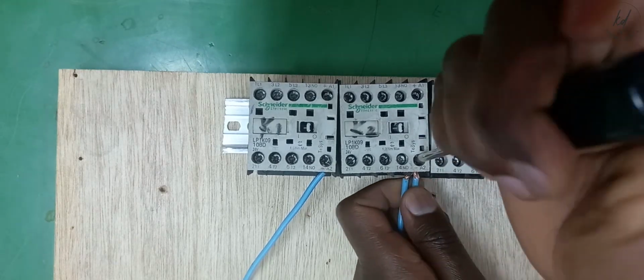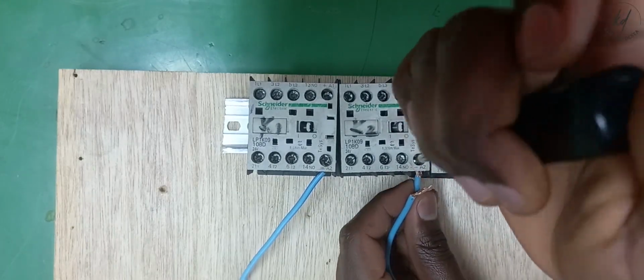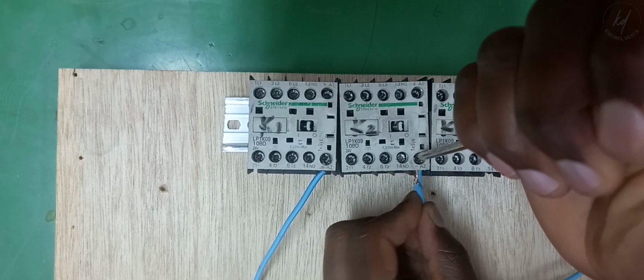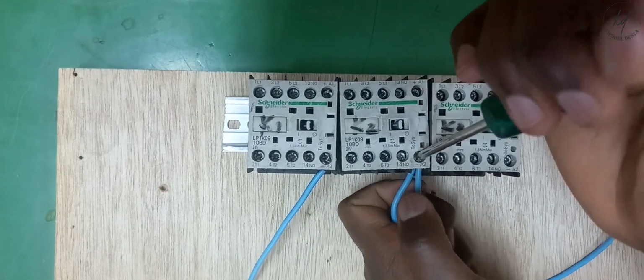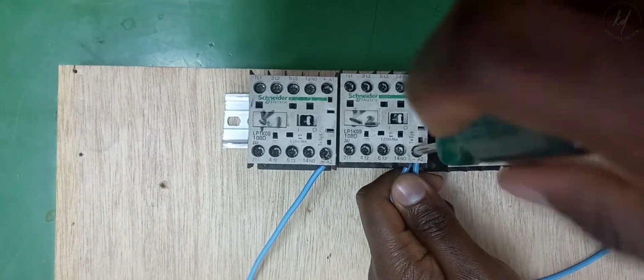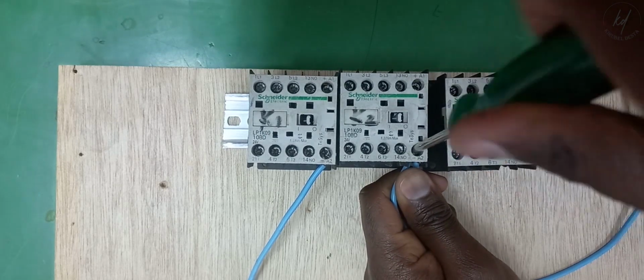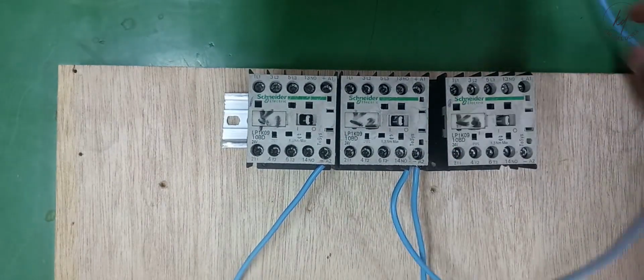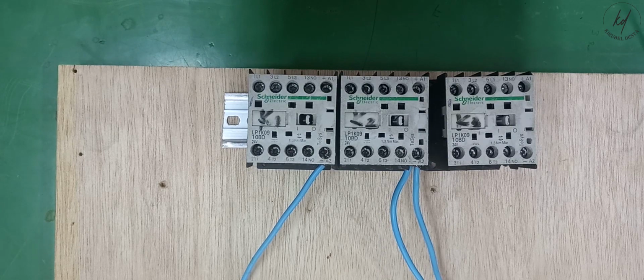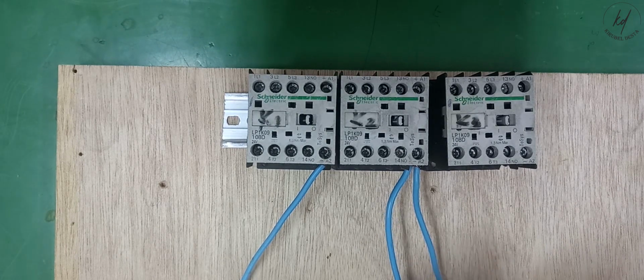Advantages of Star Delta Starter. 1. Low cost. 2. Components require very little space to build the starter. 3. Limits the starting current to 1/3 of the DOL starter. 4. Simple design and operation. 5. Comparatively cheaper than other voltage controlling methods.